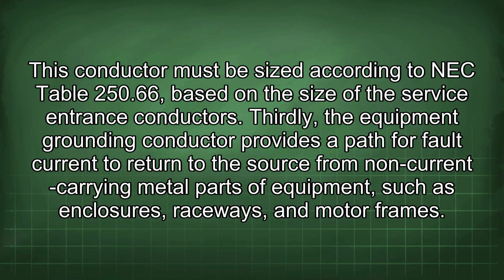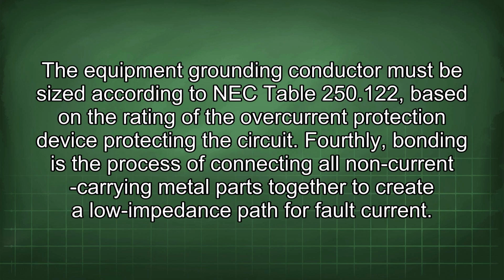Thirdly, the equipment grounding conductor provides a path for fault current to return to the source from non-current carrying metal parts of equipment, such as enclosures, raceways, and motor frames. The equipment grounding conductor must be sized according to NEC Table 250.122, based on the rating of the overcurrent protection device protecting the circuit.